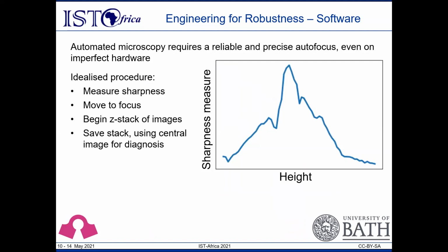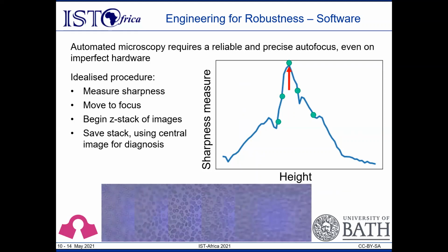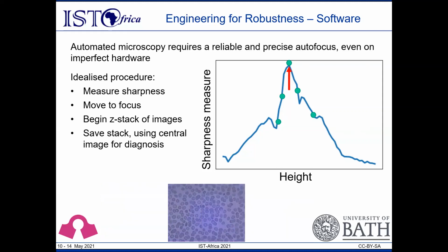To demonstrate the idealized way that autofocus could work, imagine moving the optics towards a sample and measuring the sharpness. Once you identify the sharpest point, you found the focal point, and you can move the optics back to that point to collect a sharp image. Or for blood samples, you can start collecting what we call a Z-stack. Move below the focal point and take an image, then move back up in regular steps, taking more images. The central image in this stack will be at the focal point you found and will be the sharpest, and you can use this for diagnosis. The other images in the stack can be used later to assess how well the system focused.